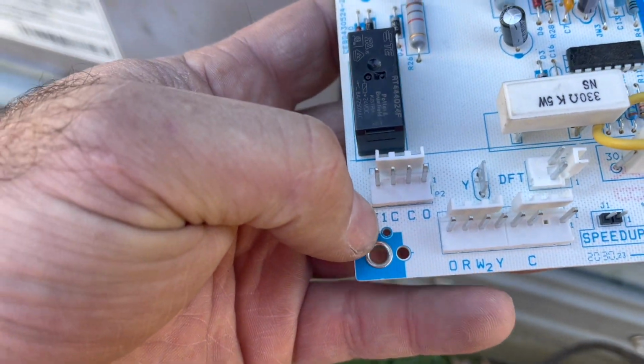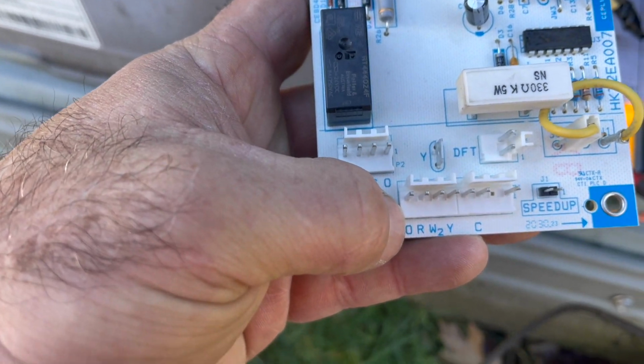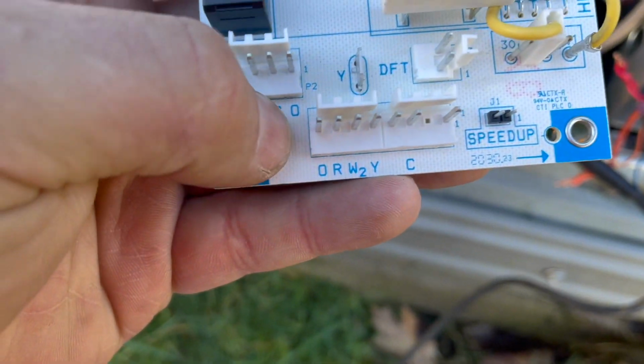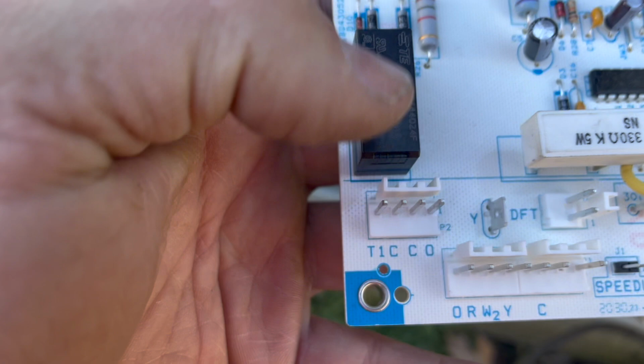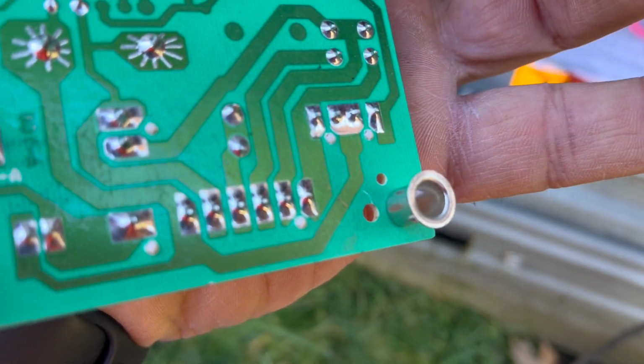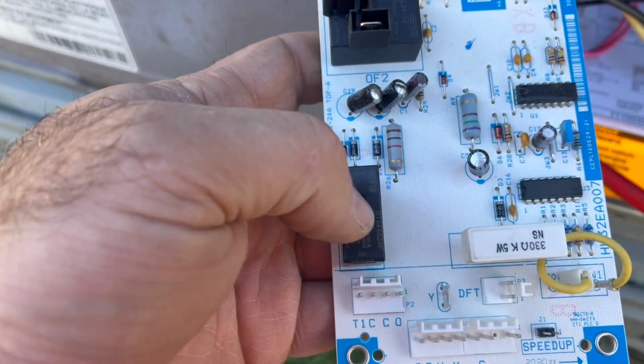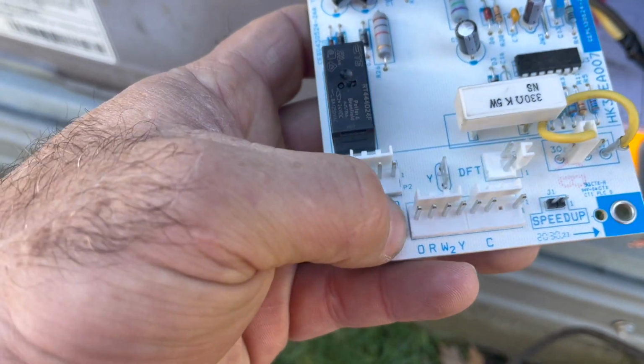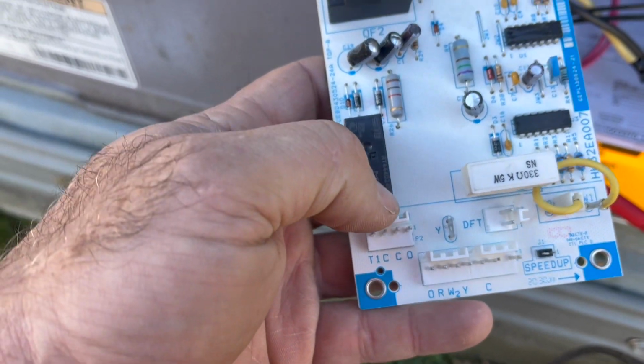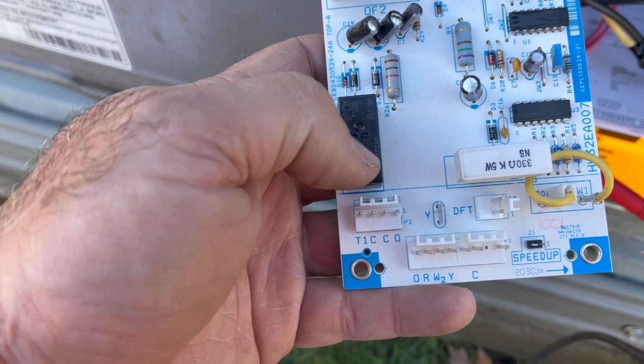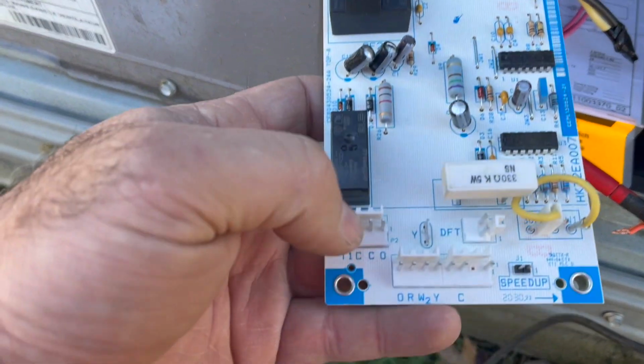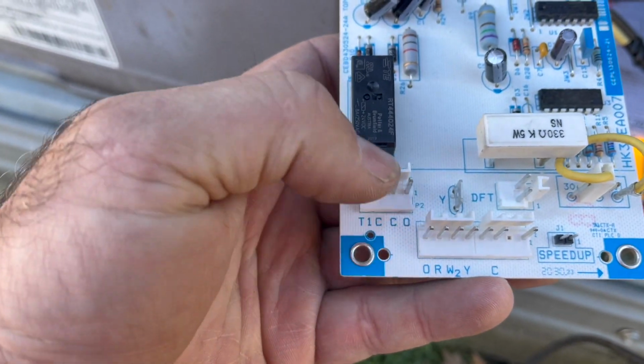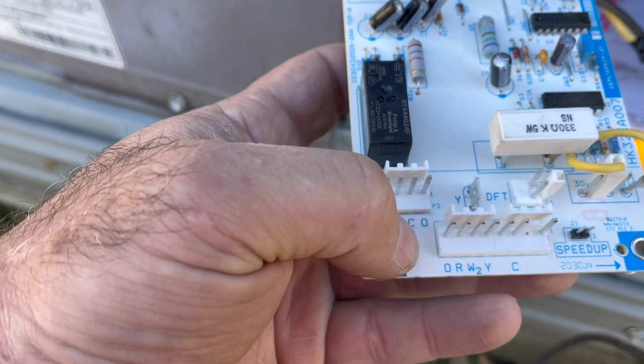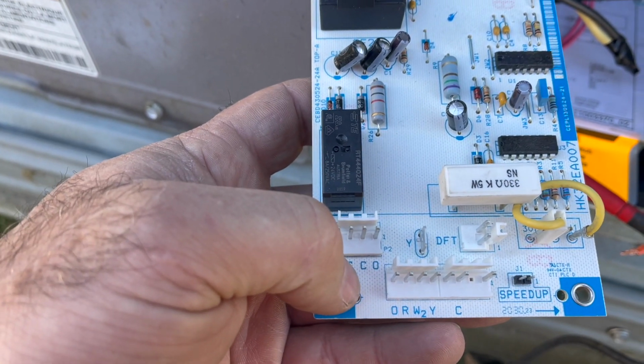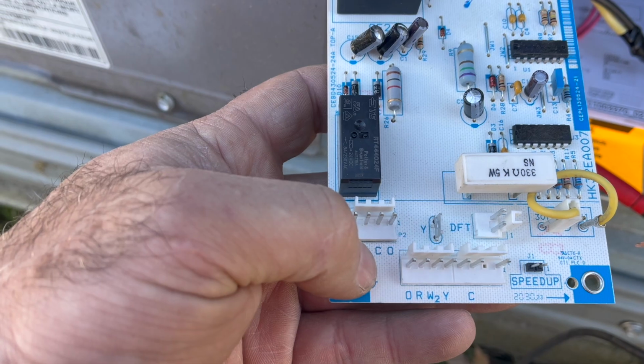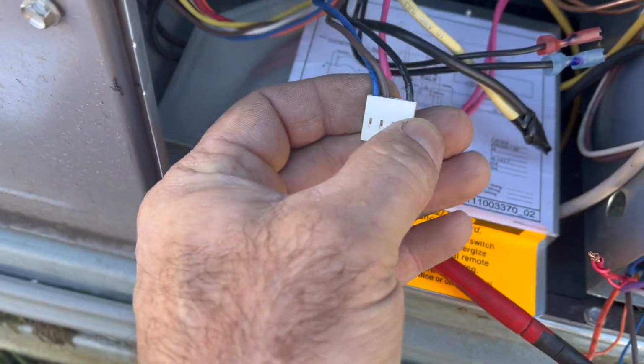But the orange comes in here from the thermostat wires, and you see an O on that little smaller connector. They're just connected together and also hooked to this relay. Basically, it either passes it through, or that relay can energize it if it needs to go into defrost. So we'll have to check on this small connector from O to common in order to see what the ohms of the reversing valve is.